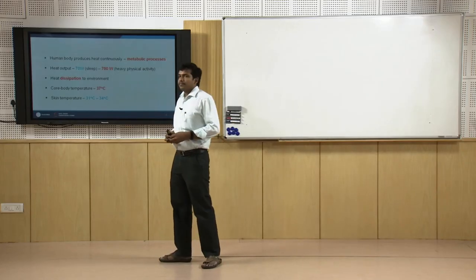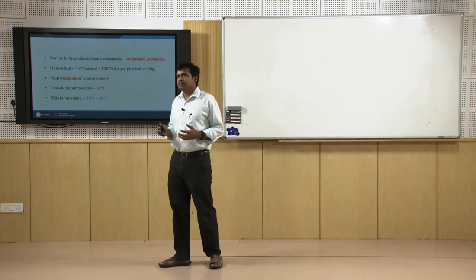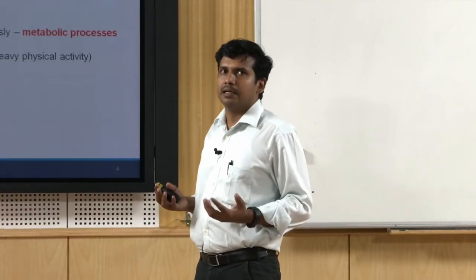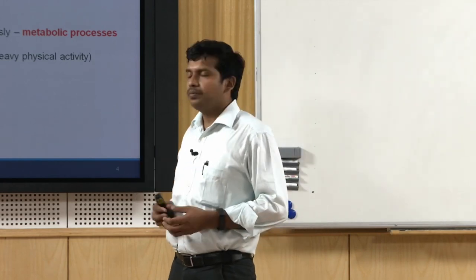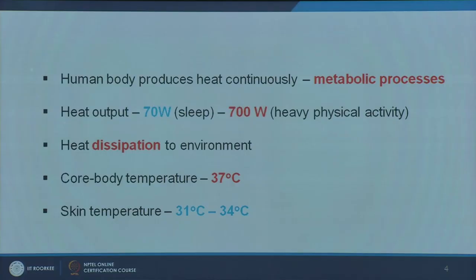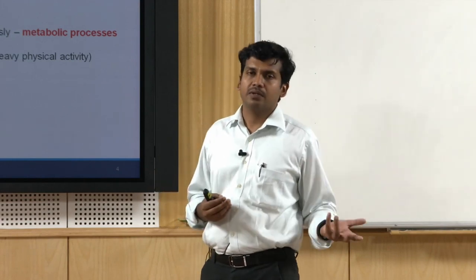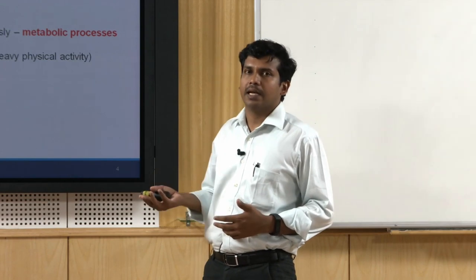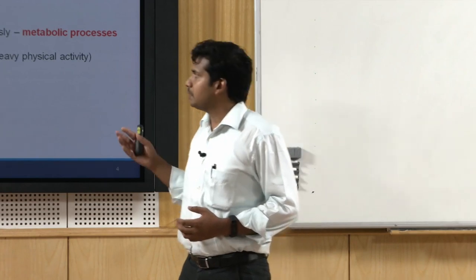The human body produces heat continuously — it is like a machine. We call it the metabolic process. As a part of this process, there is continuous heat generation, because of which heat emission and dissipation happens. The heat output varies somewhere between 70 watts during sleep and up to 700 watts during heavy physical activity. It depends primarily on what kind of activity you do — sitting in a class versus doing some physical activity or going for a jog — the amount of heat dissipation considerably varies.